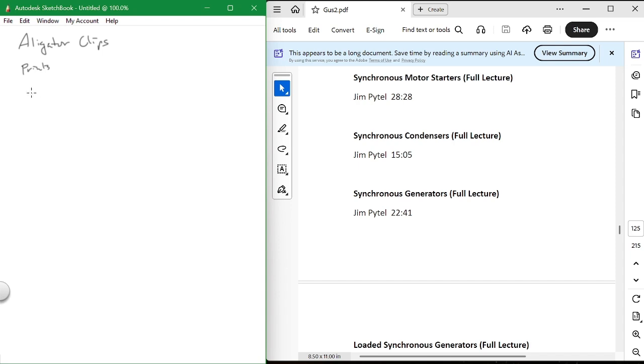That type of thing. And then you're not going to ask, you're just going to say, I'm going to go out and look at the motors, and I'm going to inspect all the motors. Okay? And you're looking at the nameplate of the motor, and you're going to get the full load amps, FLA, and you're going to make a list of FLA for your motors. Now, much to your surprise, maybe not to your surprise, the plan of the motor that was on the drawing originally and the actual motor may not be the same.